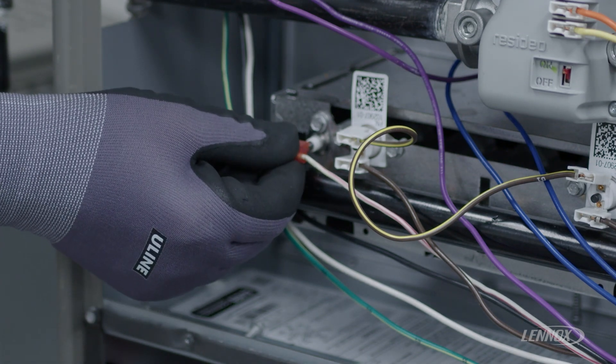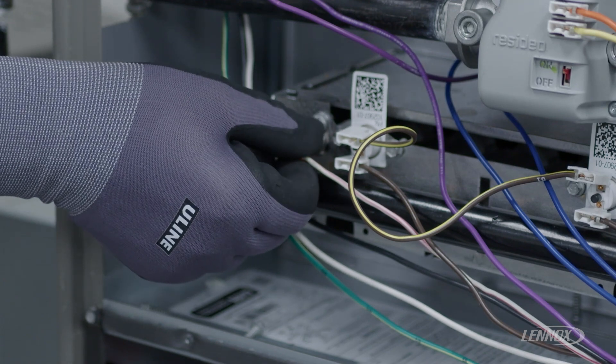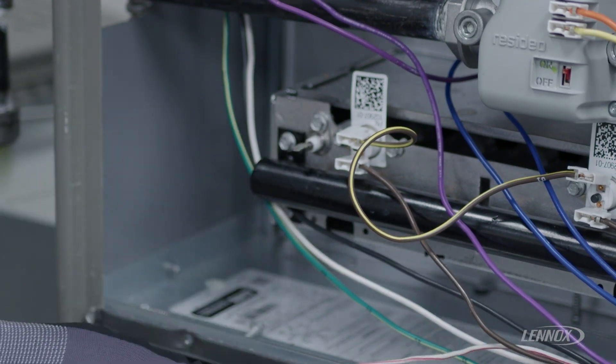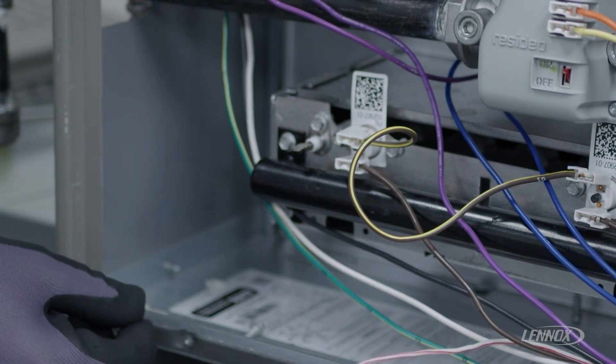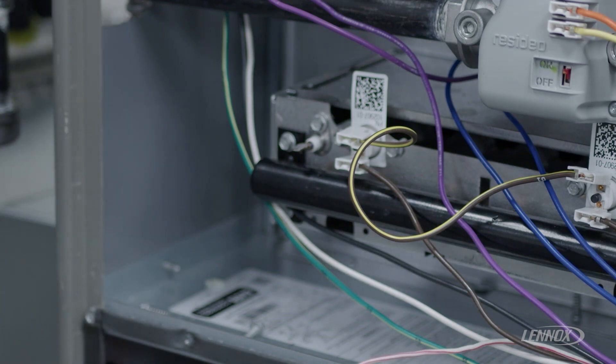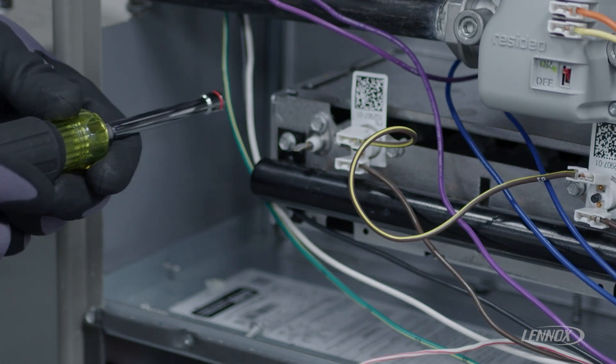As you notice in this furnace, this is the flame sensor. We want to disconnect the flame sensor lead from the 5/16 spade. You'll notice that it's connected with one quarter inch screw holding it to the burner assembly.